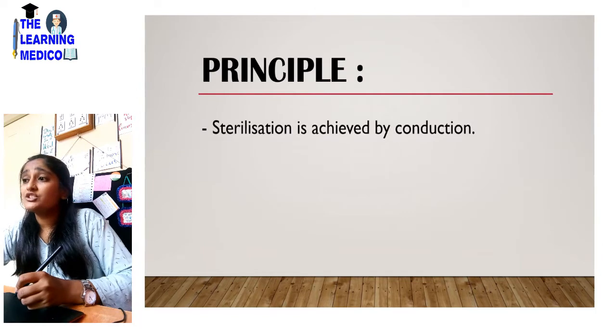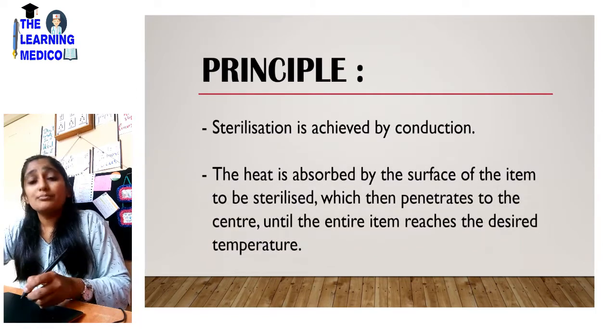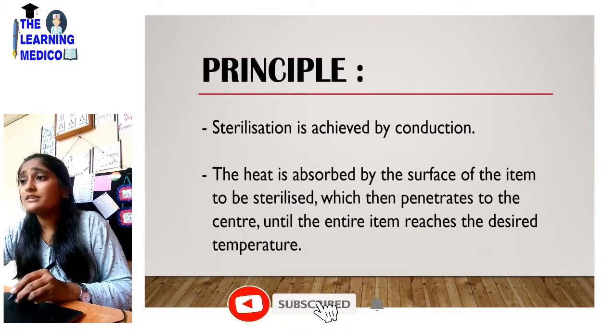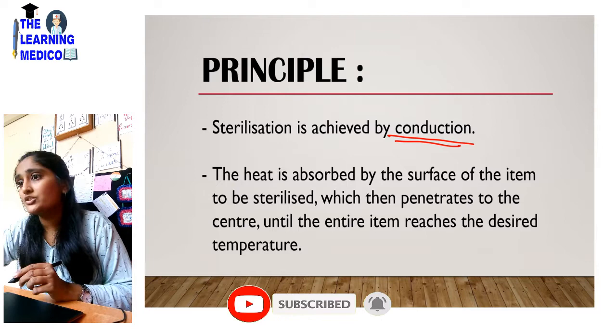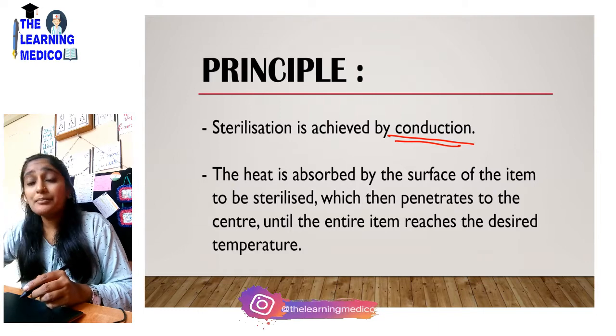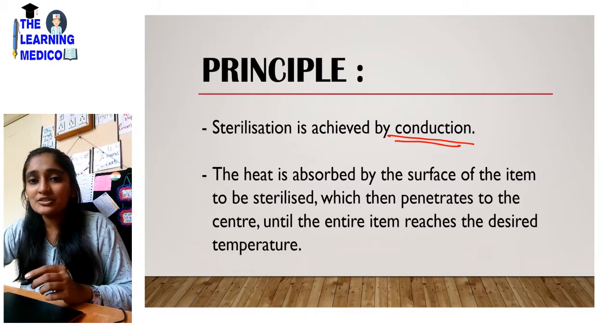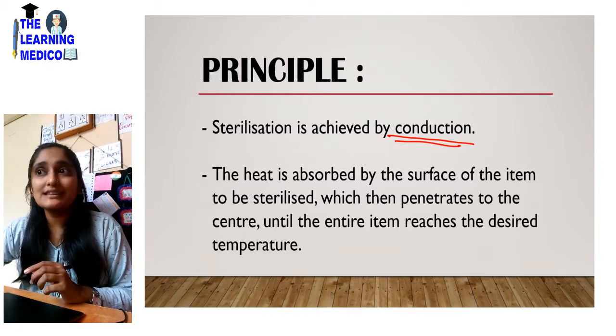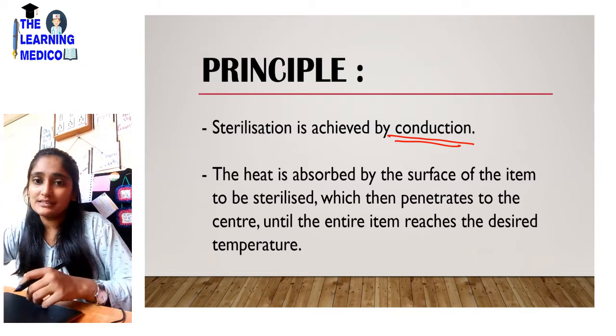The principle: sterilization is achieved by conduction. What happens in Hot Air Oven sterilization? The heat is absorbed by the surface of the item to be sterilized, which then penetrates to the center until the entire item reaches the desired temperature. When you look at the procedure, you will understand the actual principle.